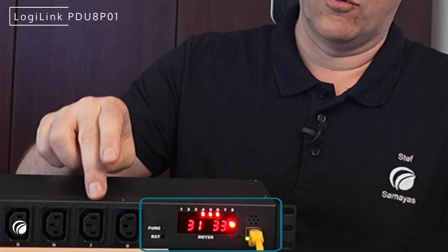When I first powered on the PDU, to my annoyance, there was a static IP address assigned to it, and it totally ignored my DHCP server. The default IP address is 192.168.0.10, so you need to change your PC's IP address in order to modify the PDU's IP.